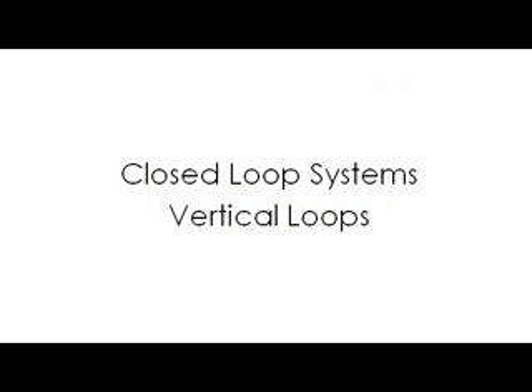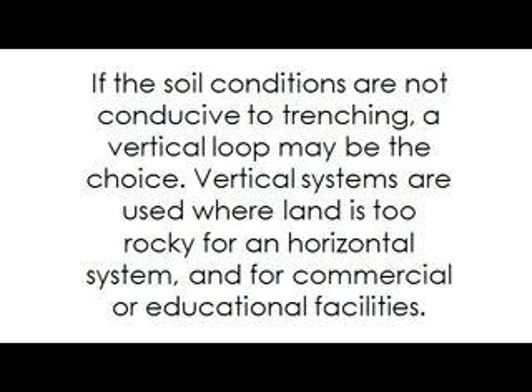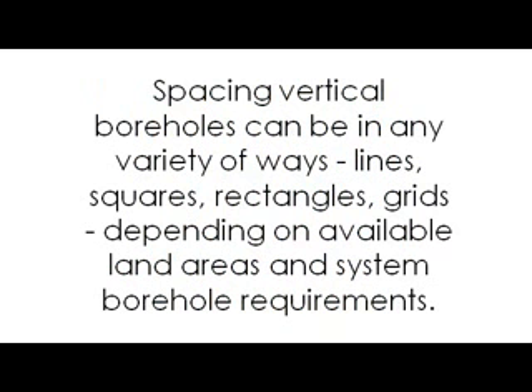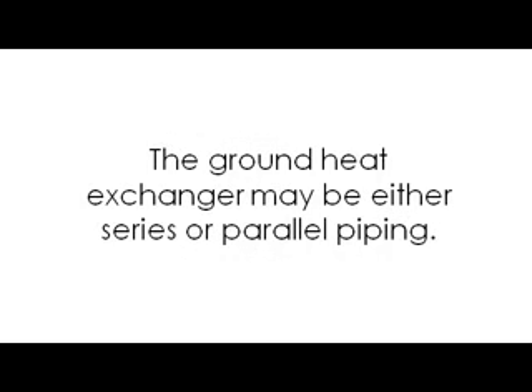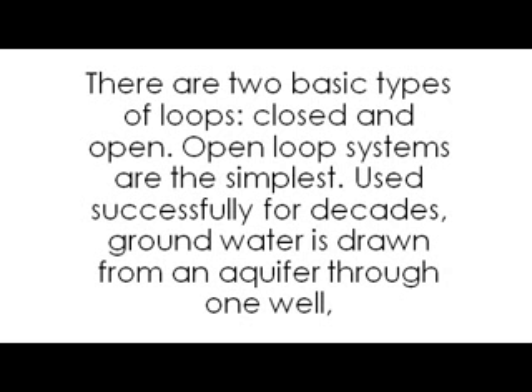Closed-loop systems, vertical loops. If the soil conditions are not conducive to trenching, a vertical loop may be the choice. Vertical systems are used where land is too rocky for a horizontal system and for commercial or educational facilities. Spacing of vertical boreholes can be in any variety of ways: lines, squares, rectangles, grids, depending on available land area and system borehole requirements. The ground heat exchanger may be either series or parallel piping. Closed and open loops. There are two basic types of loops: closed and open.